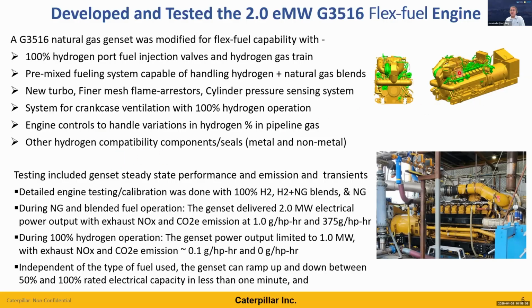Once this genset was fully put together, we took it to our large engine test cell at Southwest Research Institute and did detailed testing on this multi-cylinder engine. During natural gas and blended fuel operation, the genset delivered the full 2 megawatt electrical power output, as it's supposed to do. NOx and CO2 emissions from that operation were about 1 gram per horsepower-hour and 375 grams per horsepower-hour respectively.